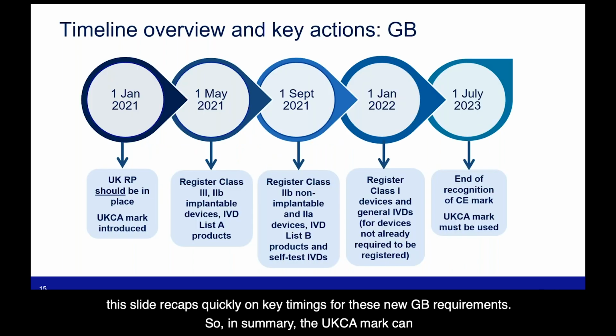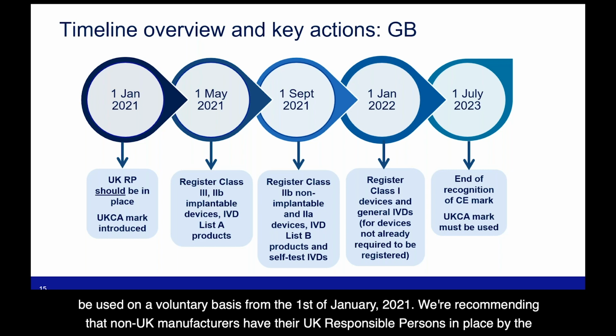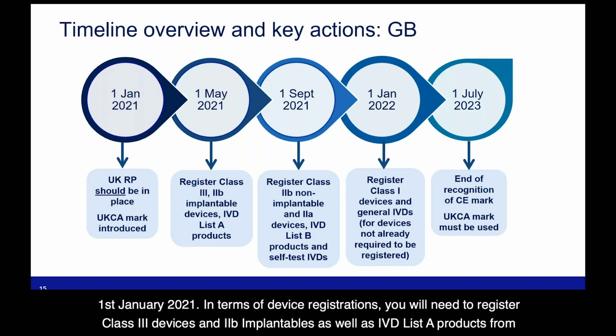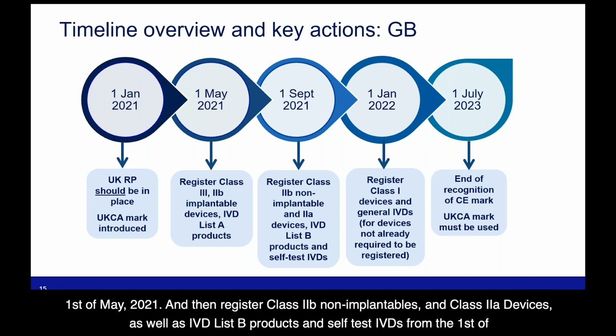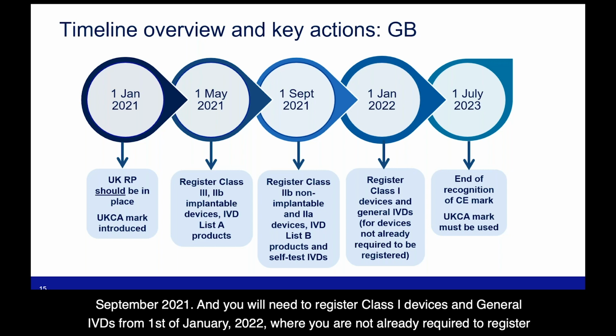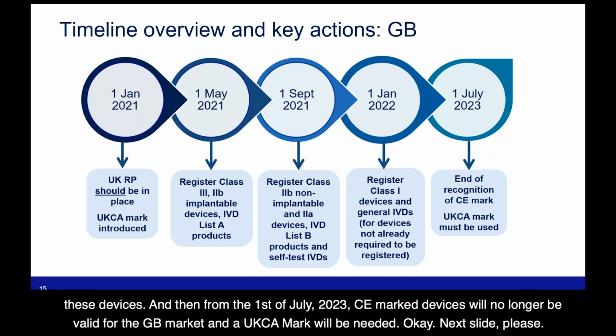So this slide recaps quickly on key timings for these new GB requirements. So in summary, the UKCA mark can be used on a voluntary basis from the 1st of January 2021. We're recommending that non-UK manufacturers have their UK responsible persons in place by the 1st of January 2021. In terms of device registrations, you will need to register Class 3 devices and 2B implantables, as well as IVD List A products from 1st of May 2021, and then register Class 2B non-implantables and Class 2A devices, as well as IVD List B products and self-test IVDs from the 1st of September 2021. And you will need to register Class 1 devices and general IVDs from 1st of January 2022, where you are not already required to register these devices.